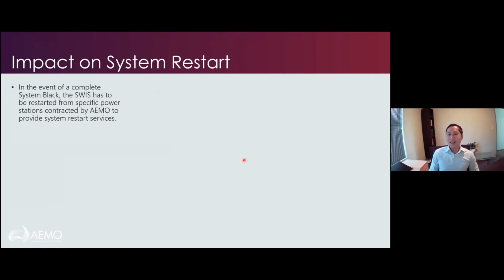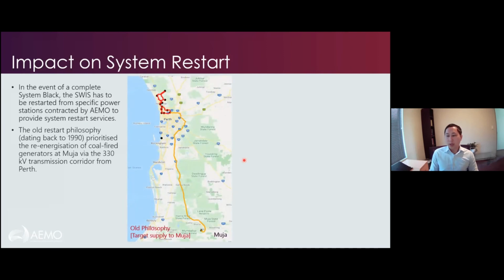Lastly, the impact of DER on system restart. We had the unfortunate situation of going to a system black condition, requiring restart from specific power stations contracted for system restart services. The old restart philosophy, going back to the 90s, prioritized re-energising coal-fired power plants in the Collie Basin area around Muja, starting from one restart source and building a loop to energise a large 330kV line out to Muja.